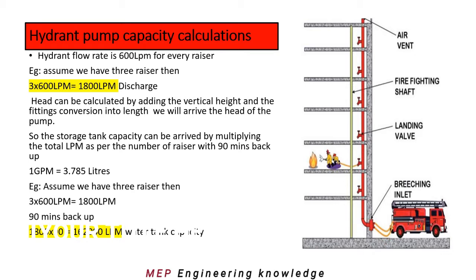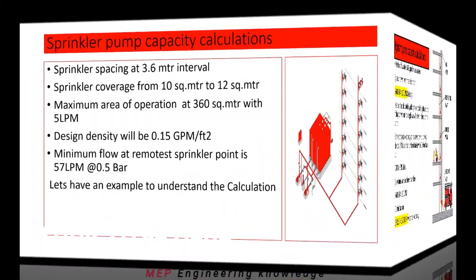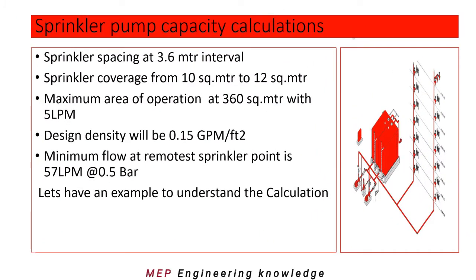The fittings can be arrived at by using the chart available for converting fittings into equivalent pipe length. The storage tank capacity can be arrived at by multiplying the total LPM as per the number of risers with 90 minutes backup. Note that 1 GPM is 3.785 liters. Assuming three risers: 3 into 600 LPM is 1800 LPM, and 90 minutes backup gives 1800 into 90 = 162,000 liters — that is the water tank capacity required.